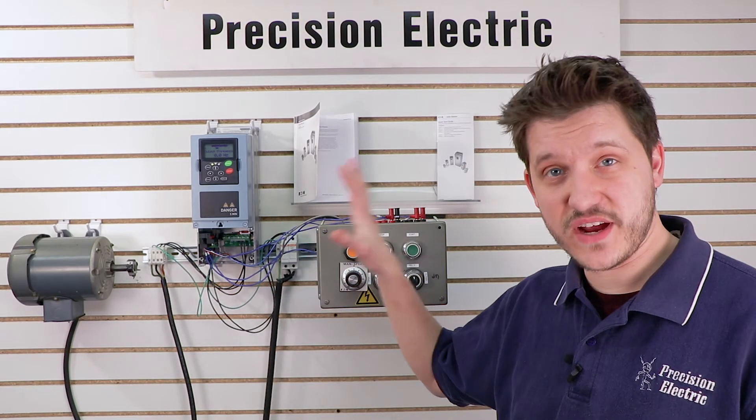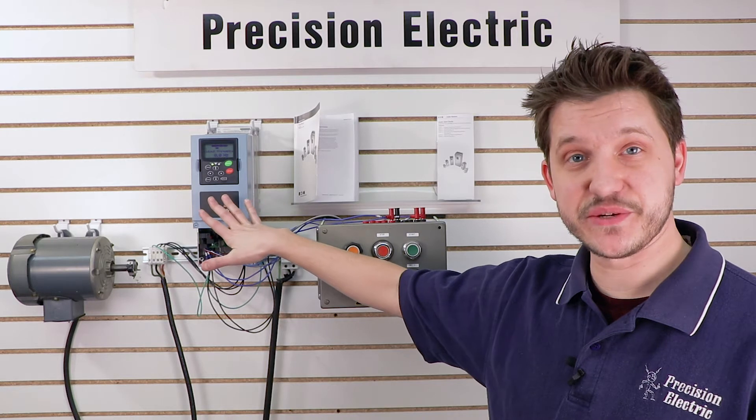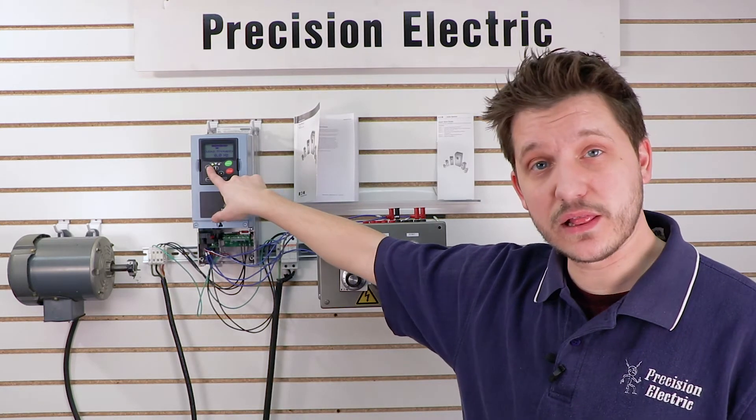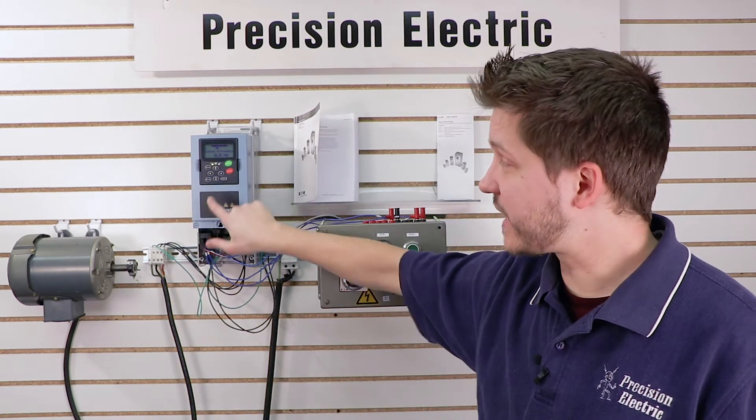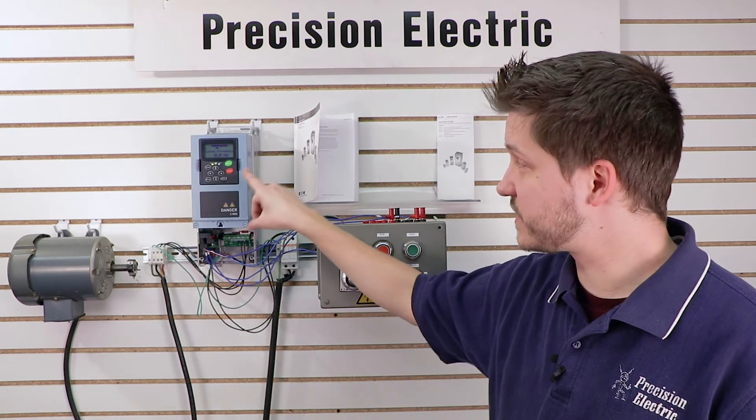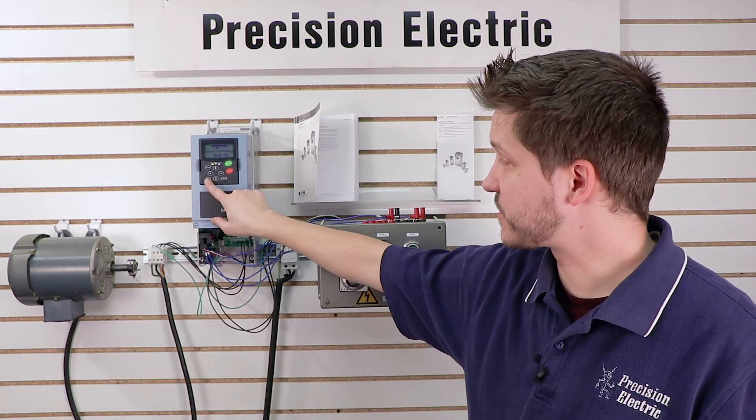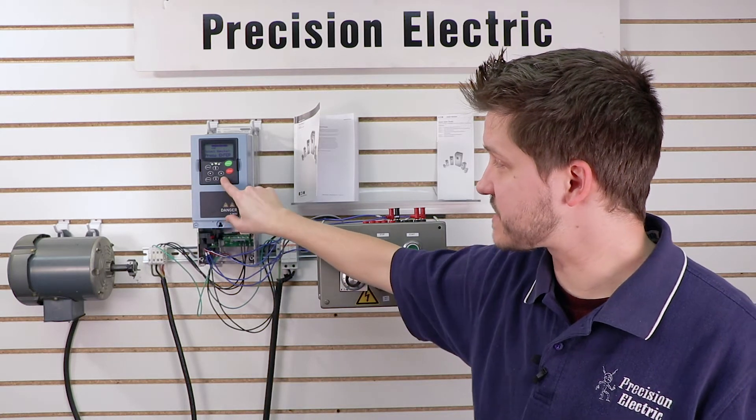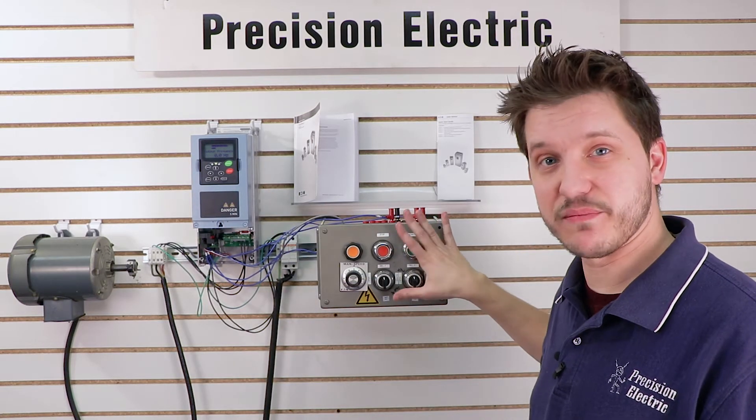Okay, so now that we're running and I've got it programmed, I've got it in operation mode, right now I'm still in local, so I need to switch from local back to remote, otherwise it's not going to look at my push button station. In local it only looks at the keypad, so I'm going to press local remote, and I'm going to press enter, which will switch to look at my terminal strip.